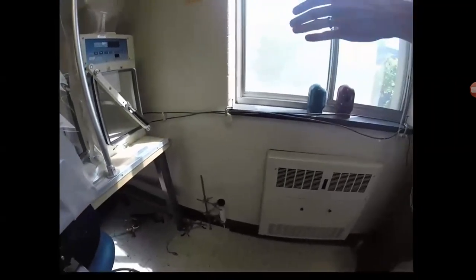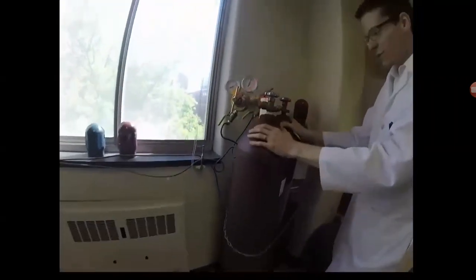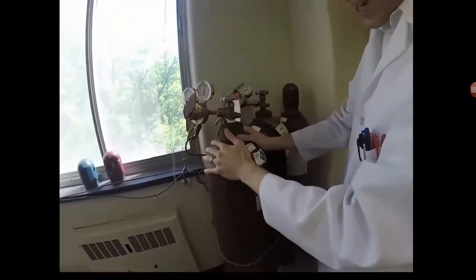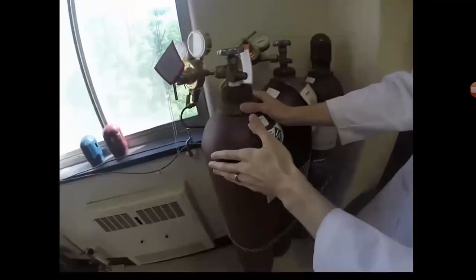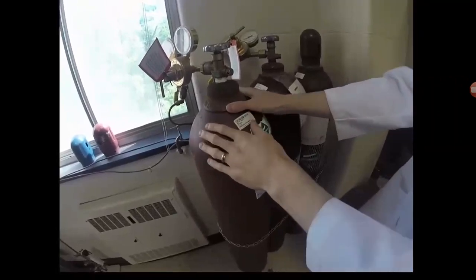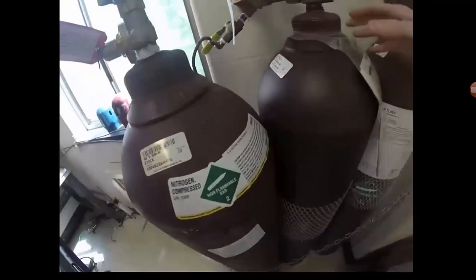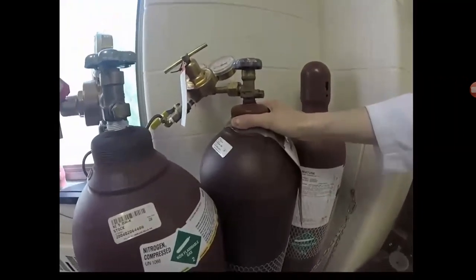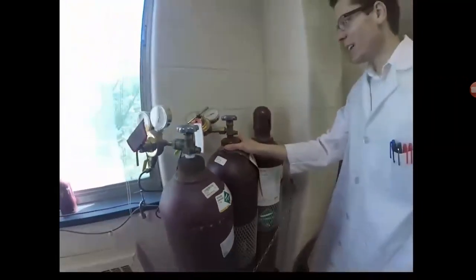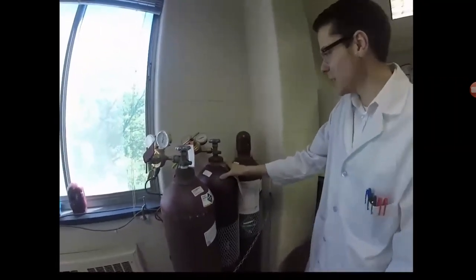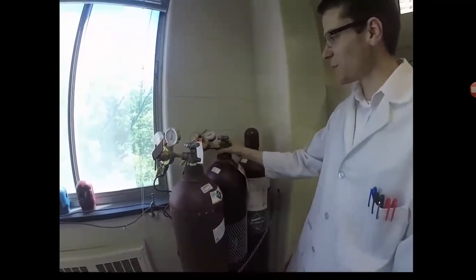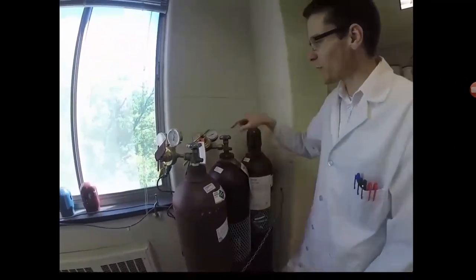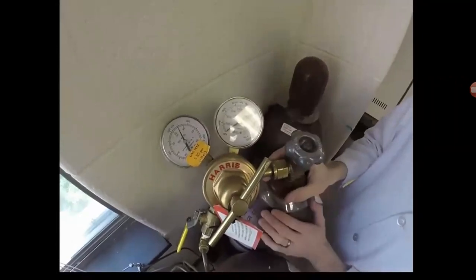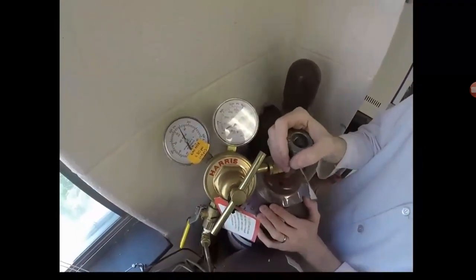There's a copper line that runs from the back of the anaerobic chamber airlock all the way over to the gas cylinders, which are located here. There's 2 types of cylinders. This one is nitrogen. It's ultra high purity, so it has relatively trace amounts of oxygen in it. This one is a mixture of hydrogen and nitrogen, so it's 5% hydrogen, and the balance is nitrogen. So it's not flammable at that point. But there are still some differences in terms of the regulator because you're working with hydrogen. Okay, so if you can see up here, our hydrogen cylinder, although it's open, is currently empty. So we need to change the cylinder before we can use it. We're going to do that real quick.